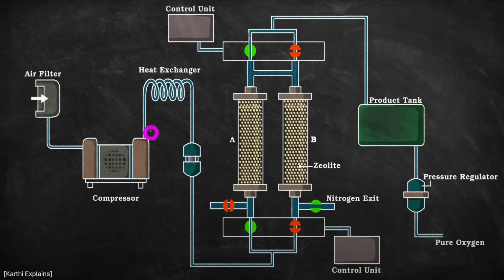Afterwards, you're going to have a compressor. Similarly, this compressor should have no oil coming out, no oil particles. It also has to be filtered. But because you're compressing the air, the temperature is going to go up, and you don't want to pass hot air through this, especially if there is a patient on the other side who is going to breathe this afterwards, and you also don't want to heat up the zeolite. So there's some heat exchanger to make sure the air passing through the next stage is at least back to room temperature. There's some pressure regulator here to control what's going on. And then we have 2 tanks of zeolite, which is going to become clear exactly why that is.